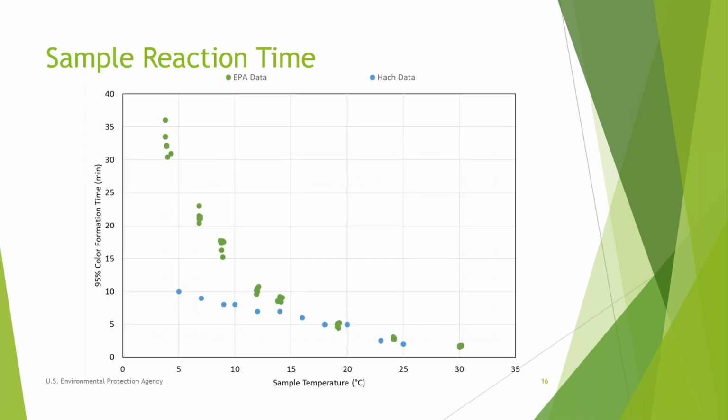So for the next 2 slides, I'm going to talk about the sample reaction time findings that Matt discussed earlier in his presentation. So the monochlor-F reagent reaction time is strongly influenced by the sample temperature. And so the purpose of this study was to assess the influence of the sample temperature on the reagent reaction time prior to analysis using this indophenol method.